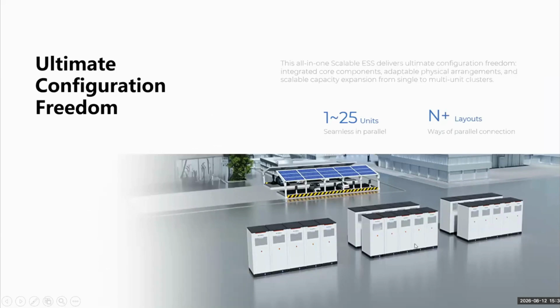And for the layout, this is just a sample. It can support side by side, so it is seamless and can save a lot of space on site. It can also support face-to-face or back-to-back. For face-to-face, we usually recommend around 2.5 or 3 meters, and suggest the customer reserve enough space to open the door or for future maintenance. For back-to-back, we recommend at least 600 millimeters for heat dissipation. And if some of the cabinets are configured with an explosion venting panel, when installed back-to-back the distance between two units will extend from 600 millimeters to 1 meter.